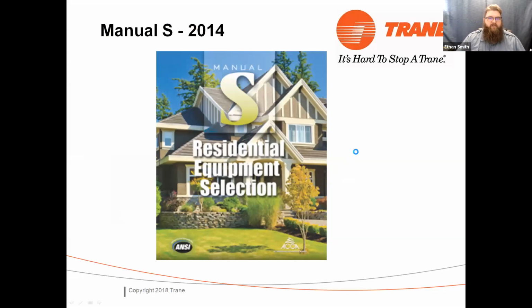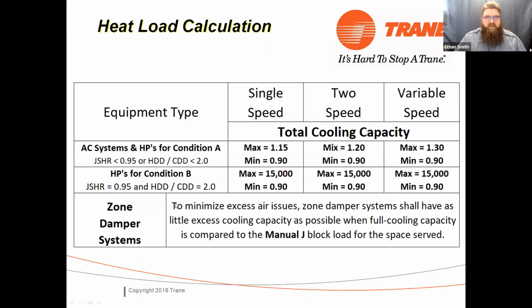So when we get into Manual S, which is our equipment selection part, these are some rules of thumb. So guys that are taking notes, take a picture of your screen, do whatever you want to do. But here's your rules of thumb with sizing equipment. So AC systems and heat pumps, you know, we talk about your single speed units should be a maximum oversized of 1.15, so 115%, and a minimum total load of 0.9. Okay, that's just normal stuff. Okay, once we get into 2-speed systems, we can max that out at 1.2, so 120% of our sized load, or a minimum of 0.9, so 90%.